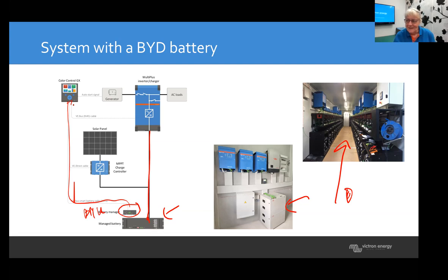But it needs to be done, because if the battery is flat, we need to stop charge, stop inverting, and some other bits and pieces. It's the same as a normal battery, but self-managed batteries quite often require a Color Control. For instance, if this cable were unplugged, or the Color Control isn't there, the BYD will not start up. It constantly checks whether the Color Control is there, and if not, after a minute or a few minutes or so, the BYD will stop because communication has been lost. It needs to stop, otherwise it could accidentally get discharged too far.